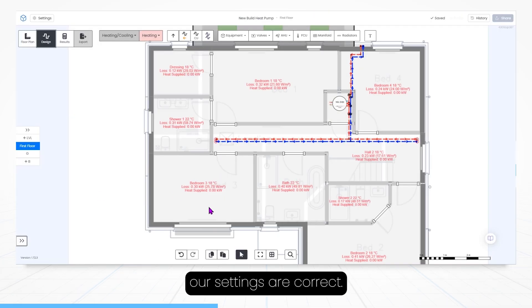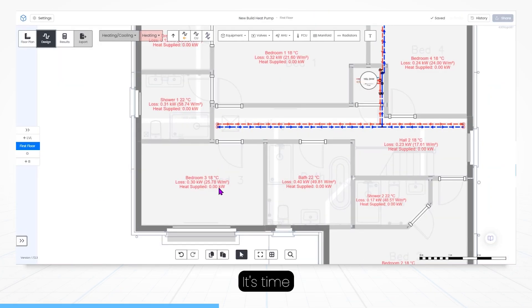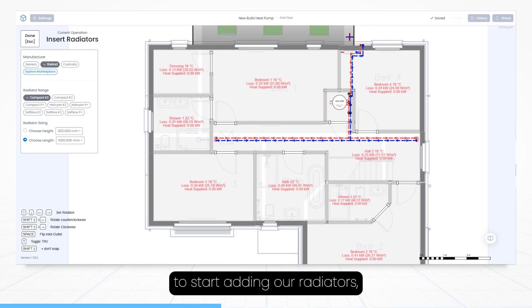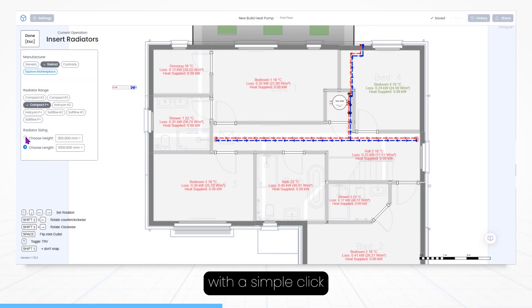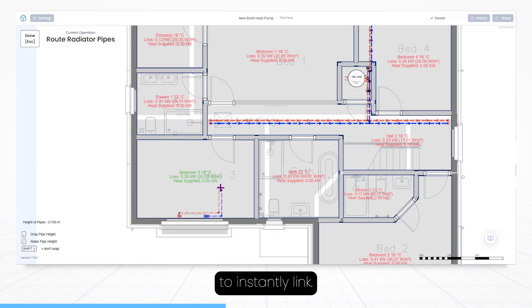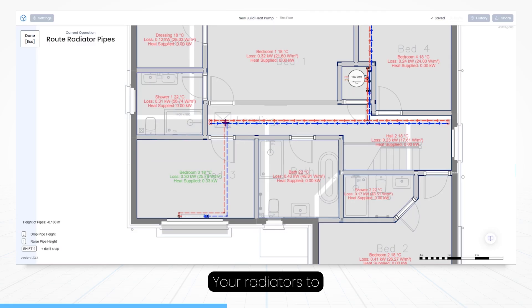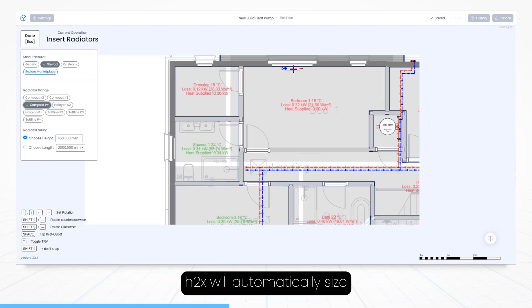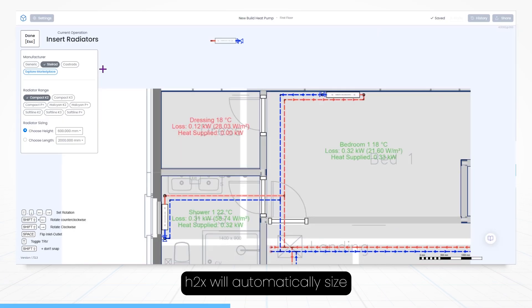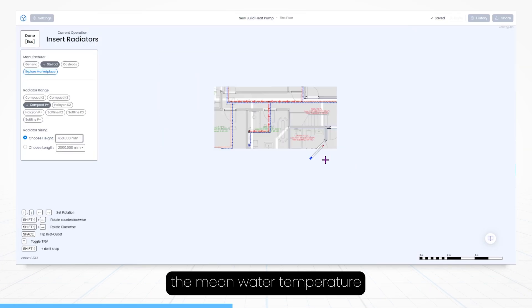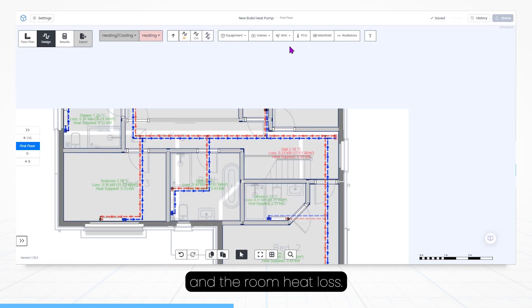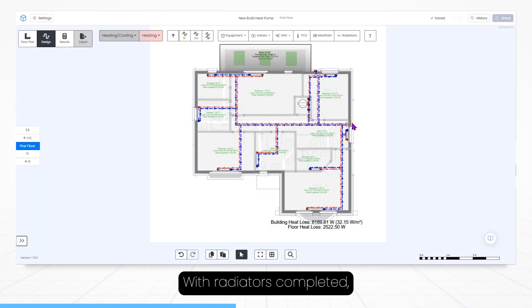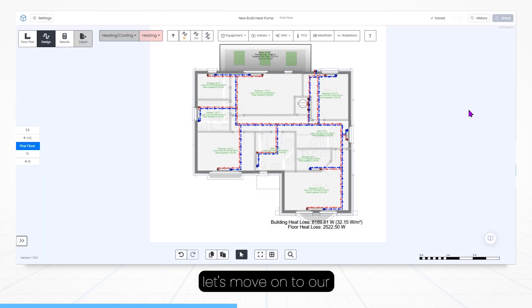Now our layout is mapped and our settings are correct, it's time to start adding our radiators, which is done with a simple click, after which you are then given the option to instantly link your radiators to your pipe system. H2X will automatically size radiators based on the mean water temperature and the room heat loss.